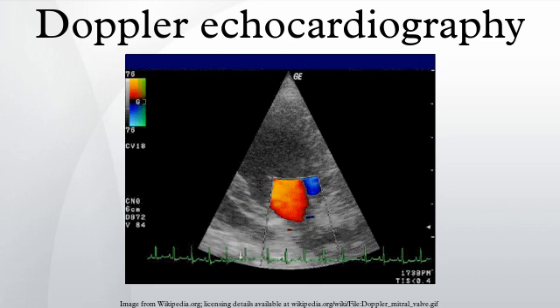Usually the median or average of multiple estimations is taken to give a more accurate result. Regarding sub-pixel accuracy: in ultrasound systems, lateral resolution is usually much lower than axial resolution. The poor lateral resolution in the B-mode image also results in poor lateral resolution in flow estimation. Therefore, sub-pixel resolution is needed to improve the accuracy of the estimation in the lateral dimension. Meanwhile, we could reduce the sampling frequency along the axial dimension to save computation and memory if the sub-pixel movement is estimated accurately enough.